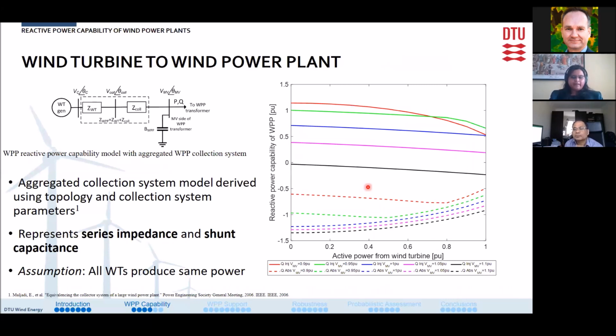So when we have the wind turbine capability curve, we extend the same model in order to get the wind power plant capability curve. In order to extend it, we include the aggregated collection system model derived using the topology and the collection system parameters of the wind power plant. The aggregation is done using the paper mentioned in the footnote here. This includes the series impedance and shunt capacitance of the whole collection system, so the losses in the system are preserved in this model. The assumption here is that all wind turbines produce the same power, so any spatial variation in wind speed due to variability in wind and wake effect are neglected.